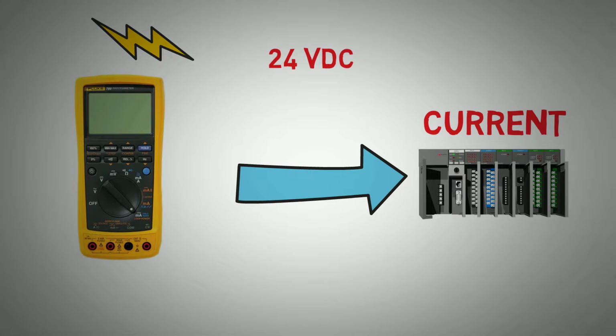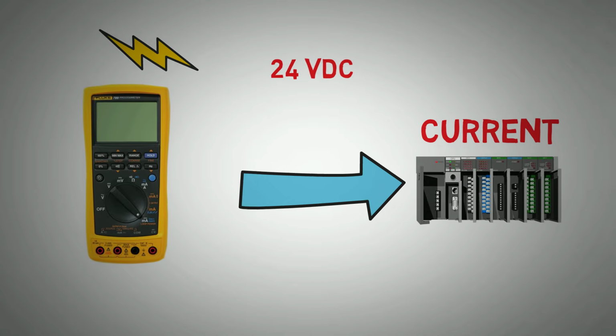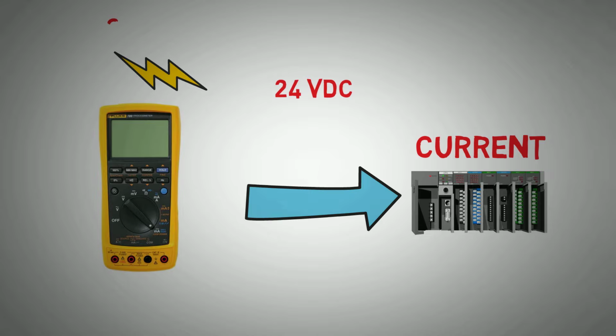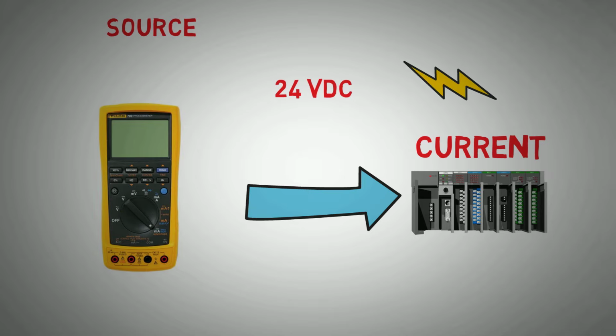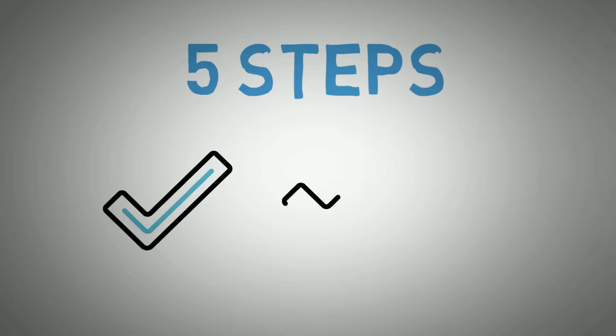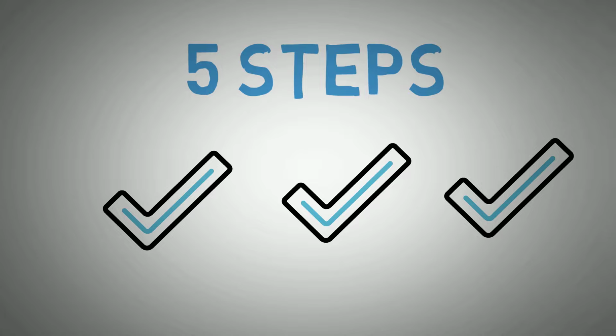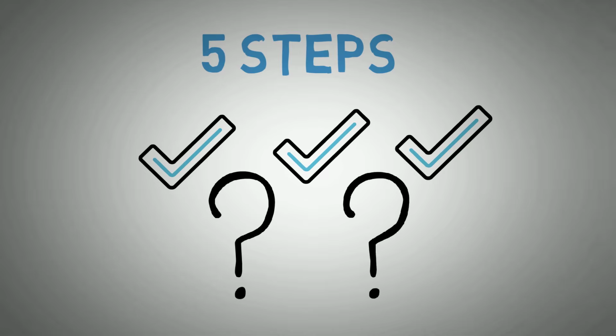When using a process meter in place of a transmitter to test the loop, you'll need to use it in a different mode depending on what is powering the loop. If the transmitter was supplying the loop power, you'll need to source the loop. If the input card or isolator is powering the loop, you'll need to simulate the loop. Let's now look at the steps you'll need to source or simulate. Afterwards, I'll go through a few tips on how to identify how a 4 to 20 milliamp loop is set up, so you'll know what mode to use.